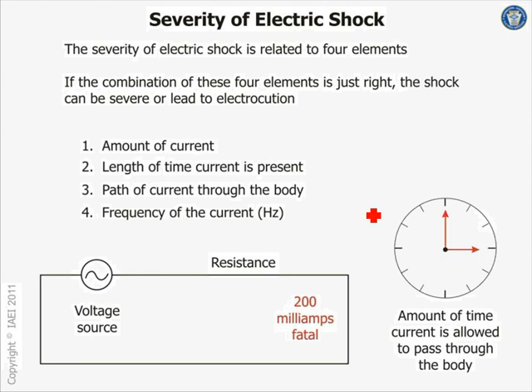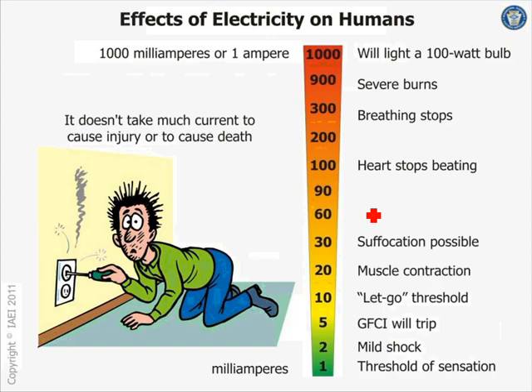Okay, so let's talk about, guys, the shock hazard. When you have a shock, the amount of current that goes through you will depend on how you are grounded. Are you grabbing phase A and phase B and standing right in there? That's the best, perfect shock. And the voltage, how much voltage? Are you grabbing 480 and 480, right? 480 voltage versus 120. So the higher the voltage, the higher the current, and the easier the path right through you will decide how fast you will join the Lord.